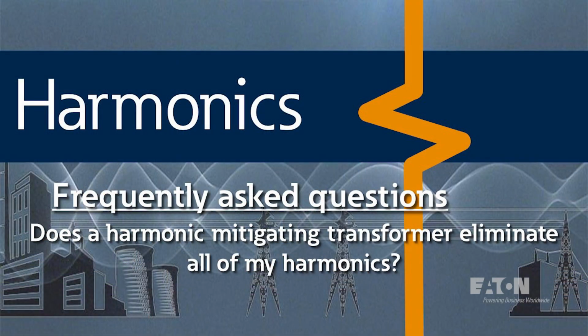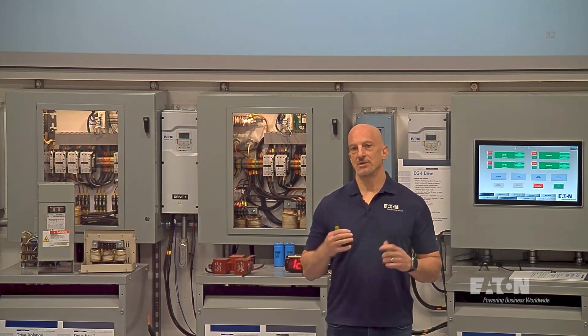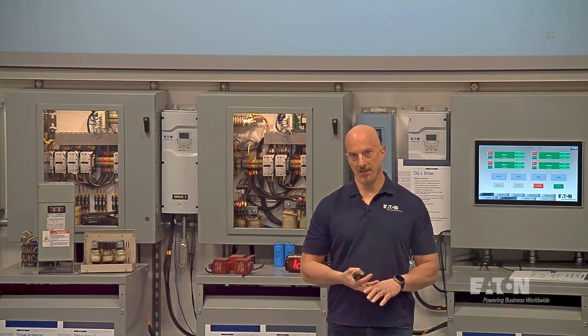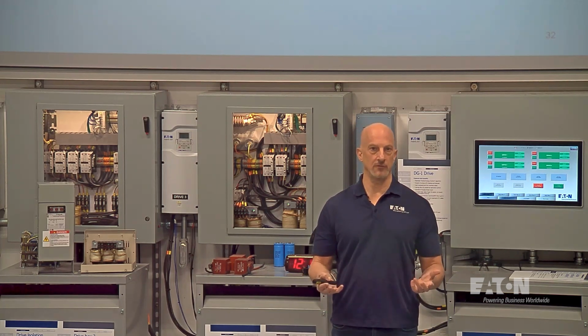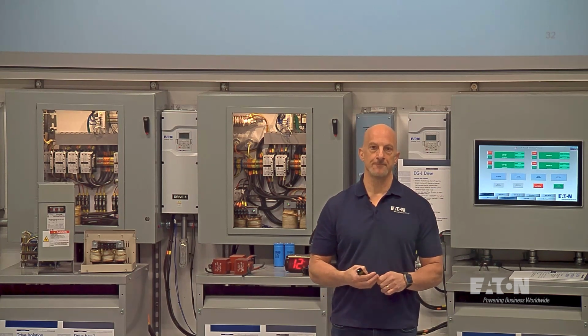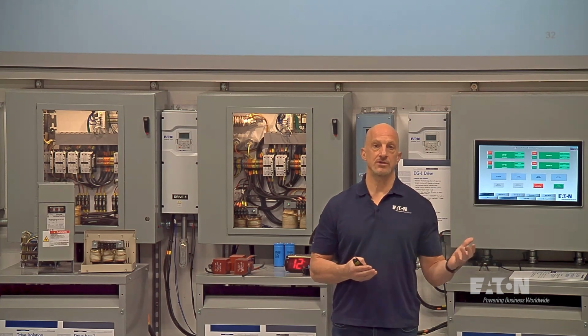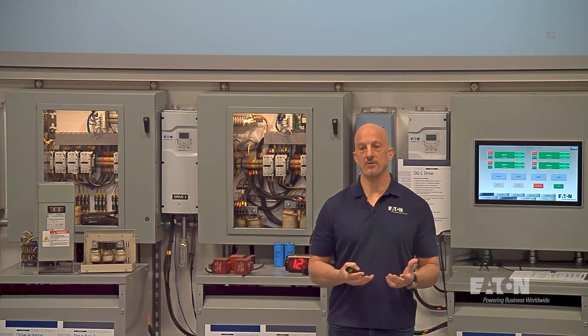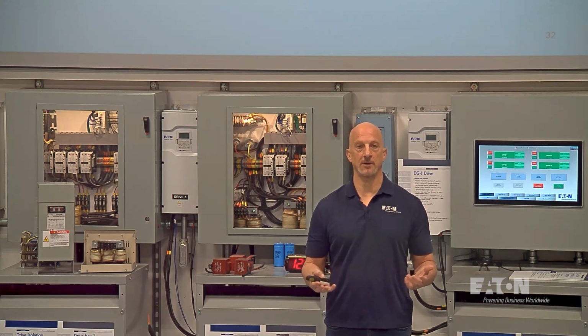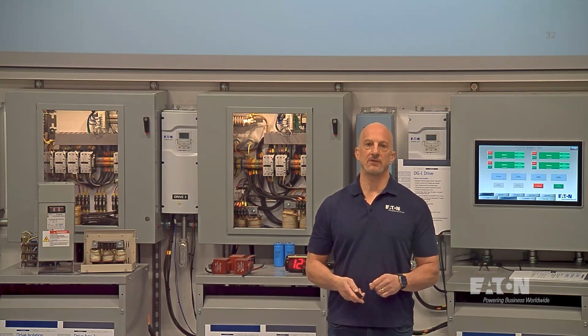Does a harmonic mitigating transformer eliminate all of my harmonics? So let's answer that question. Does a harmonic mitigating transformer eliminate all of your harmonics? And the answer is no, but you can use transformers to work together to minimize the harmonics on a power system. So there's a lot of different ways to look at it.